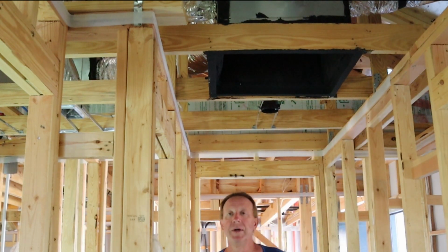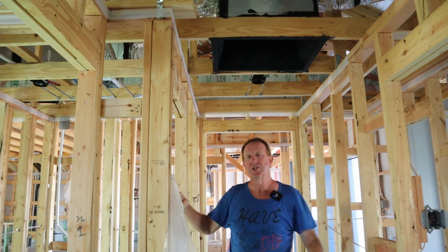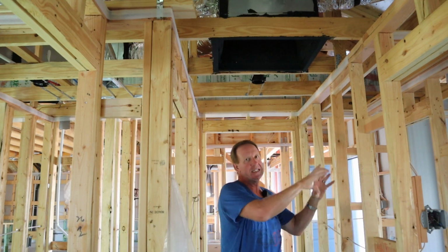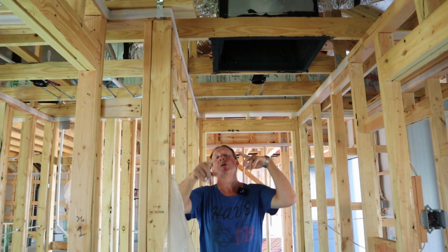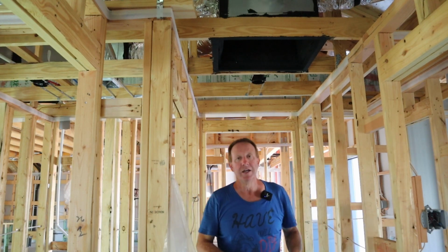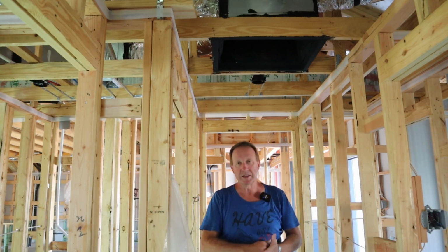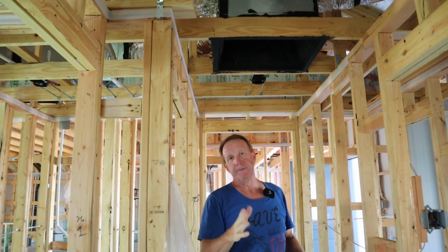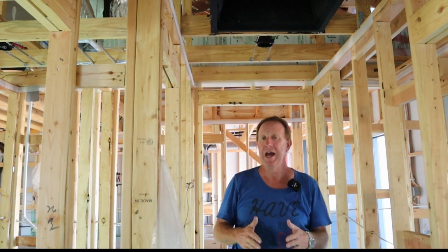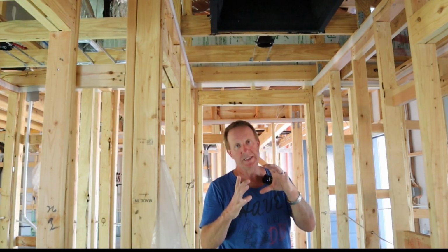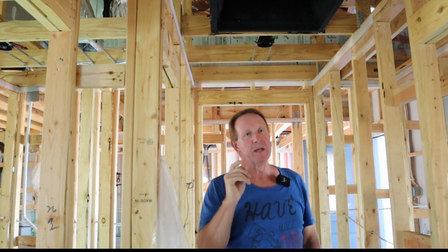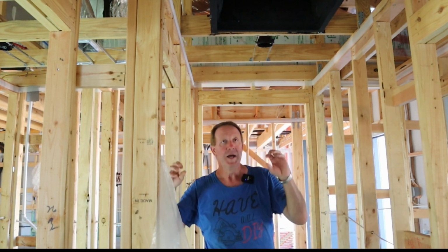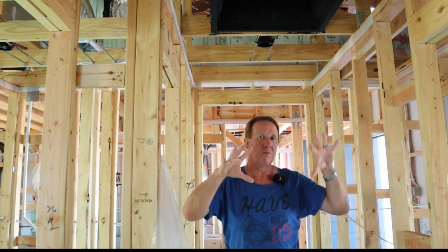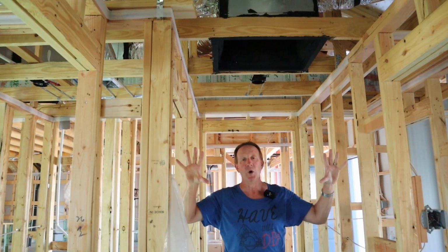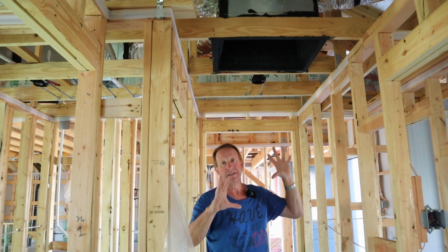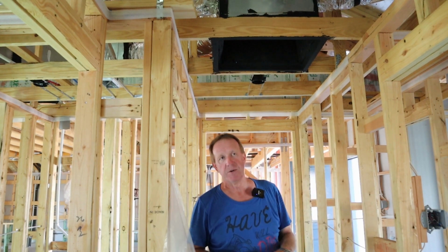Whereas the hard pipe is only so long each section, so each section has to be sealed, and then you have to come back around and insulate it. So there's a little more work, it's a little more expensive, but I like it better. Whoever you get to install your hard pipe has to be really good at getting your joints sealed up. I believe there's a material they can mist and blow into those hard pipe ducts to seal up any holes they may have missed, making them airtight, and then naturally you put the insulation around them.